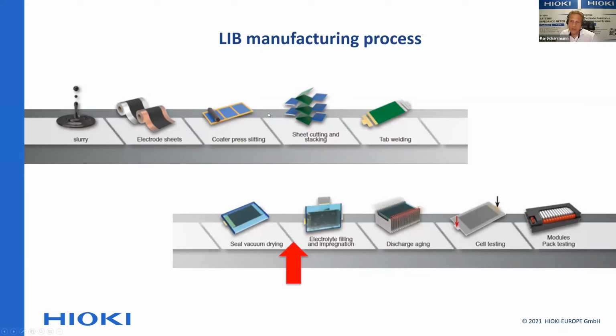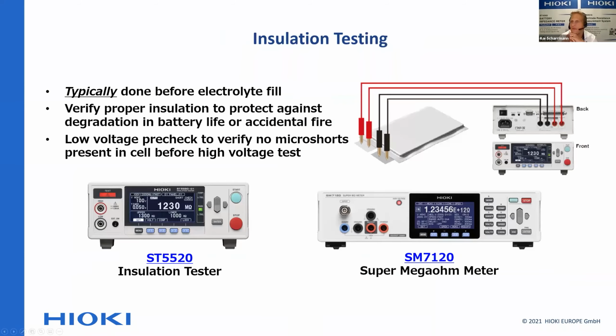We're moving on a little bit. We're moving on before we're filling the electrolyte. And sorry, again, we're not looking at battery testers yet. What we're looking at is insulation testing first, because this is typically done before electrolyte is filled. We're dealing with high voltages or high test voltages. It is not something you want to do after the electrolyte has been filled, for the simple reason that you don't want to damage the cell.